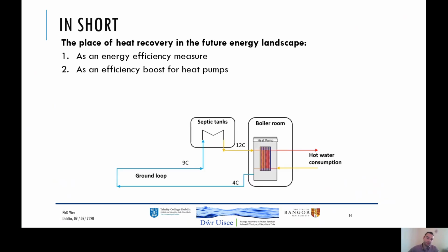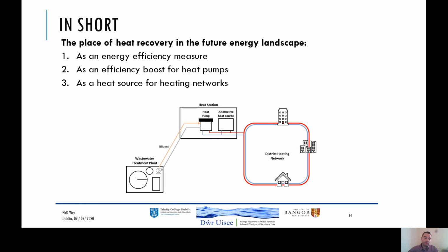Secondly, something we did not talk about is using it as an energy efficiency boost for heat pumps. The heat pump would be used in a classical way with either a ground loop or an air loop. And after this traditional loop, we would introduce it in a heat exchanger with wastewater. This would boost the temperature of the heat carrier, the example here from 9 to 12 degrees, and thus increase the effectiveness and the coefficient of performance of the heat pump. Thirdly, it can be used as a heat source for heating networks.